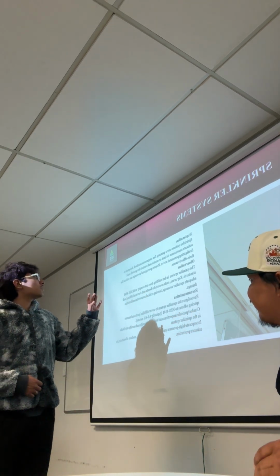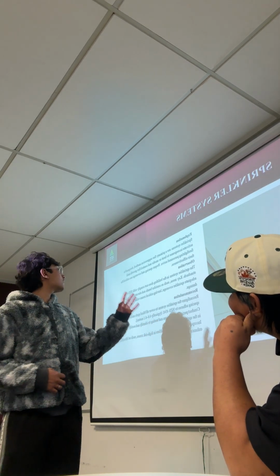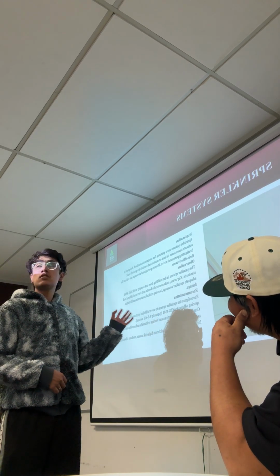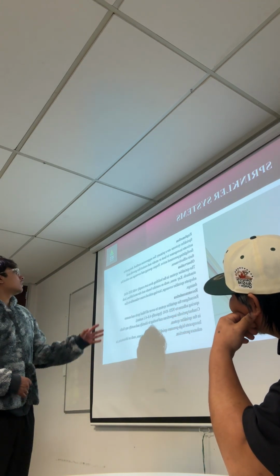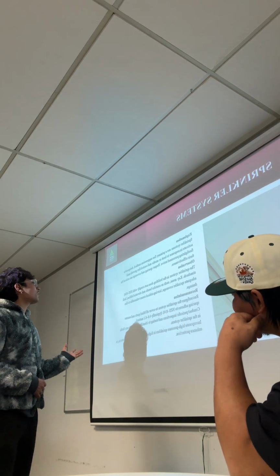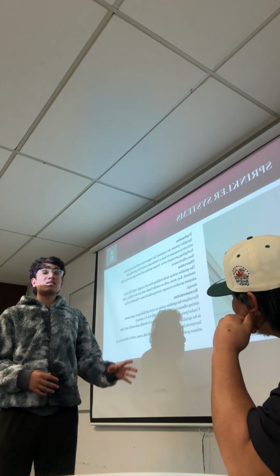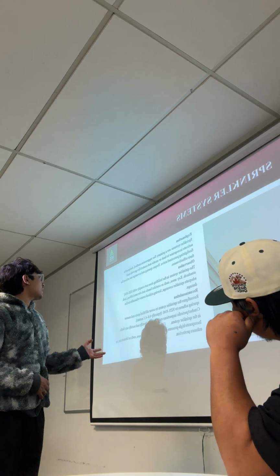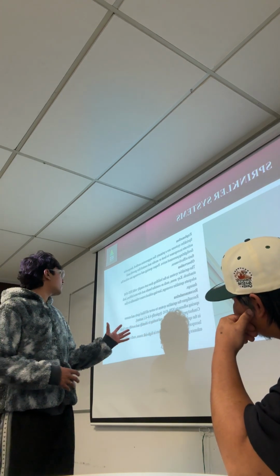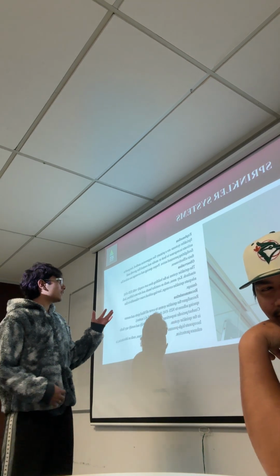So, fourthly, I would like to mention sprinkler systems. Sprinkler systems are the primary fire suppression method designed to activate in response to heat or smoke and control fire growth until firefighting personnel arrive. Proper spacing and coverage are critical for their effectiveness. The sprinkler system in the building does not comply with NZS 4541 standards. Key areas such as corridors, bends, and elevator lobbies lack adequate sprinkler coverage, leaving critical zones vulnerable to fire damage.